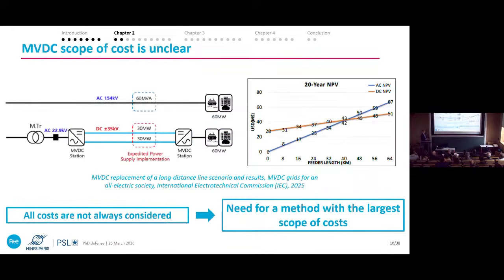When we look into the literature, there's an interesting report from a team from the South Korean TSO, inside an IEC report, comparing the connection of a 60 megawatt client either in AC with a high voltage line, or in DC with medium voltage. They derive the costs, which depend on distance, and found that at 40 kilometers, MVDC becomes cheaper than AC. There is what we call a cost break-even distance of 40 kilometers in this case.